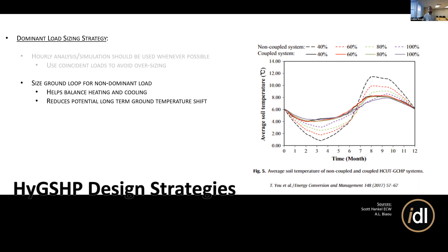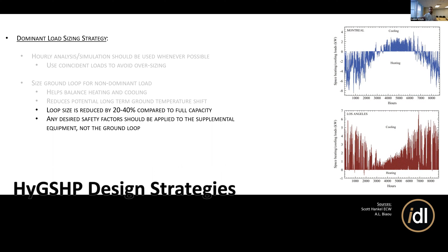And then if you do need to satisfy that engineer with an extra safety factor, add that safety factor to the supplemental system. Upsize that boiler, the extra water heater, just a little bit more. It's going to be cheaper to do that than to drill extra wells or excavate more area. And then size the supplemental system for just the remaining load.